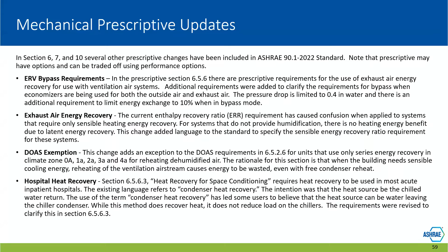And then some economizer trade-offs. We updated the table that says if you're in, say, a nonattainment area where you really don't want to bring in outside air, here's what you have to do for efficiency. So you have to go to higher efficiency. We did expand the economizer requirements down to 33,000. That's only for units that are outside a building. It's not a unit inside the building. So if you've got a rooftop, you now have to have economizers down to 33,000. They're a great energy saver, so I encourage you guys to do those.